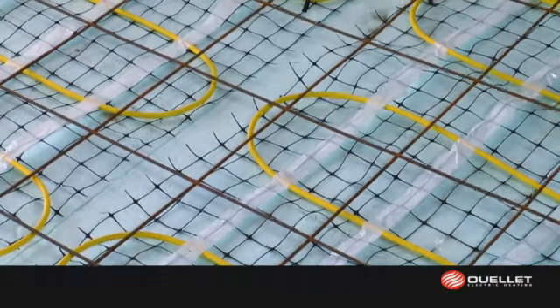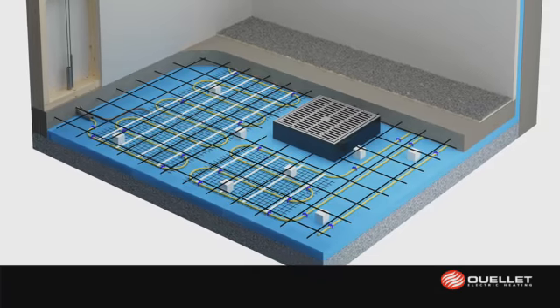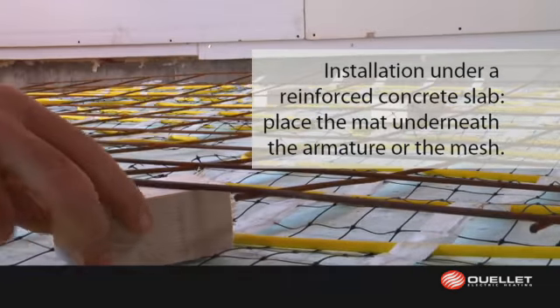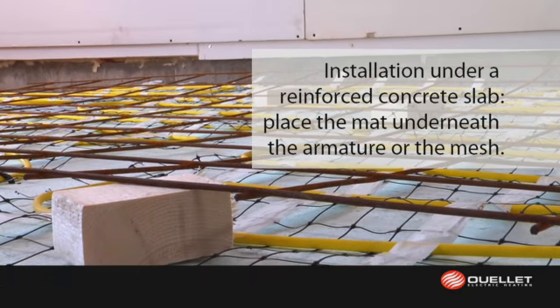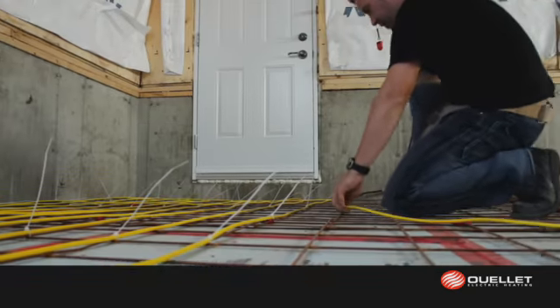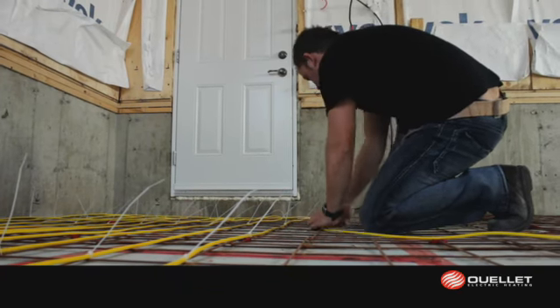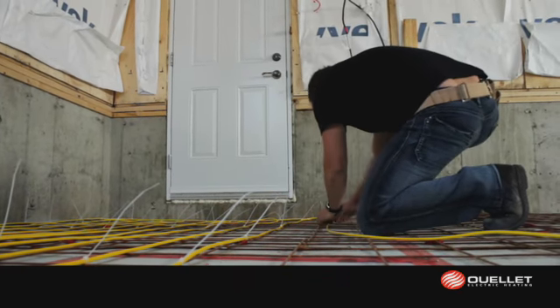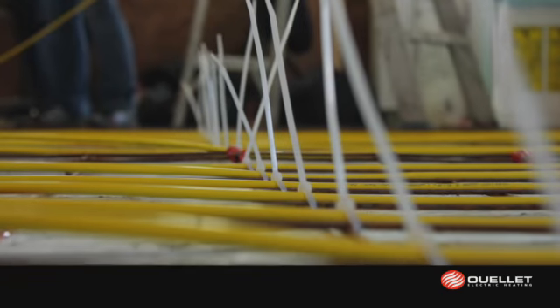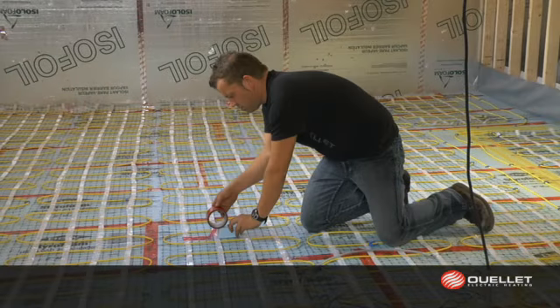The heating cable on mat lends itself really well to installations under a reinforced concrete slab. For this application, we recommend to place the mat underneath the mesh in order to facilitate the pouring of concrete. The cable on reel can also be used for installations in reinforced concrete. In this case, the cable must be tightly fastened to the wire mesh using the cable ties provided.